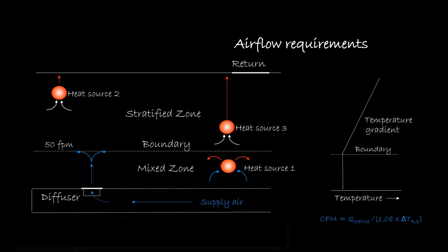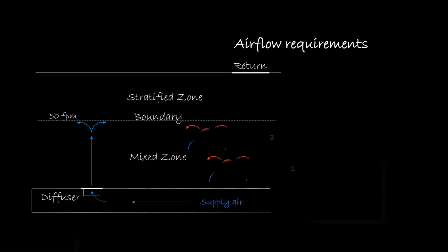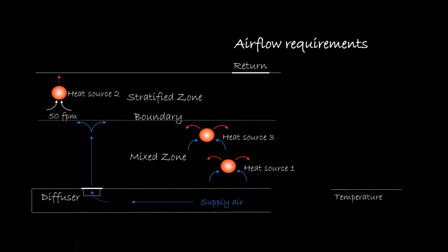UFAD supply air flow rates are dependent upon the differential between the room supply and return air temperatures. Vertical projection of the supply air jets has a significant impact on cooling airflow rates. As the vertical projection increases, more heat gains are captured and deposited in the lower mixed zone where they must be considered in the supply air flow calculations. The vertical temperature gradient corresponding to a greater jet projection might look something like this. Notice that the capture of heat gains within the mixed zone results in less stratification and thus a lower return air temperature.